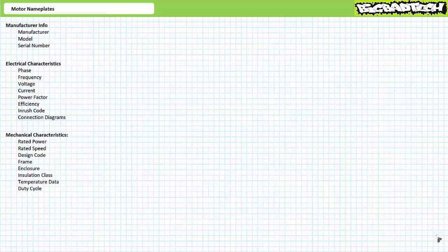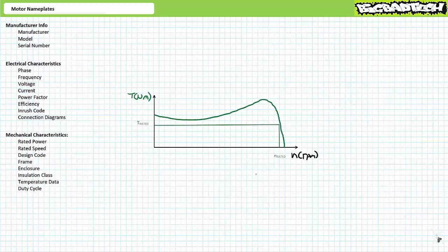There's a bunch of different information on motor nameplates, but I like to classify each piece of data as belonging in one of three different informal categories: manufacturer information, electrical characteristics, and mechanical characteristics. Some motor nameplates also feature additional optional information. This lecture will restrict itself to discussing the most common and important entries. Before we do, let me make one point absolutely clear. A motor nameplate is not a data sheet. It is a mini data sheet for one single point inside a motor's larger operational range.